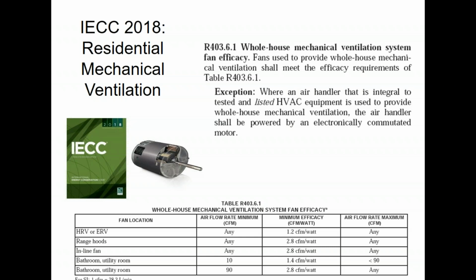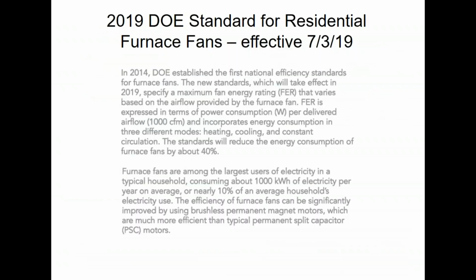You don't buy bath fans. You don't put them in the bathrooms. You put a register there and a duct, and you run that duct over to the HRV because that's the air that was going to be trash anyway. And you recover the energy out of that air, transfer it to your ventilation air. If you need help with that, let me know. We can do a discussion on that.